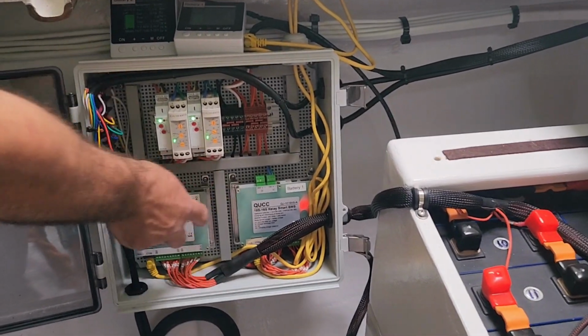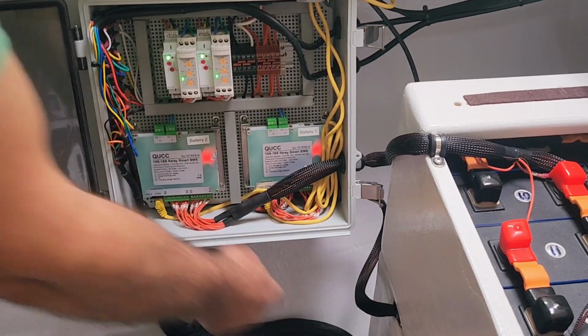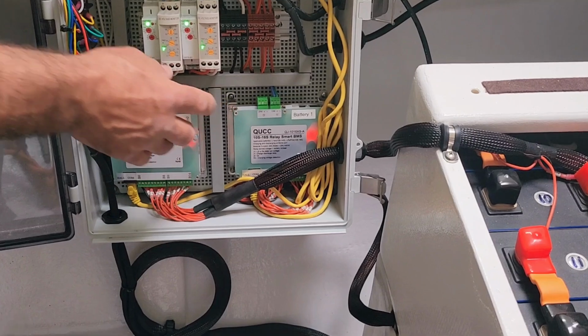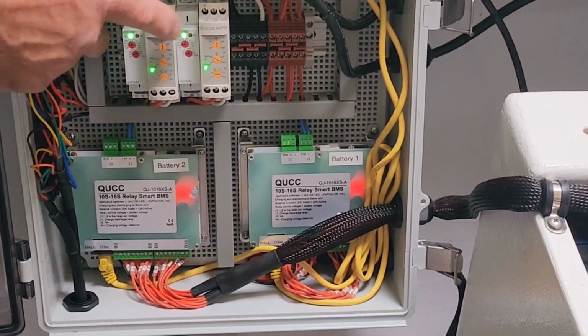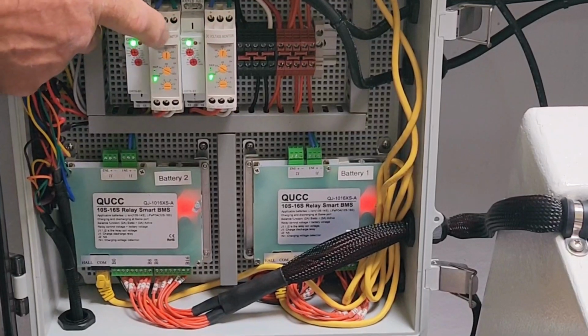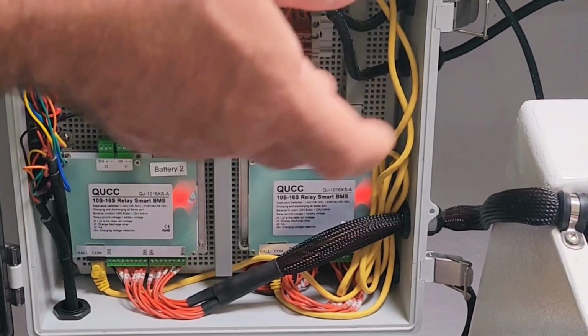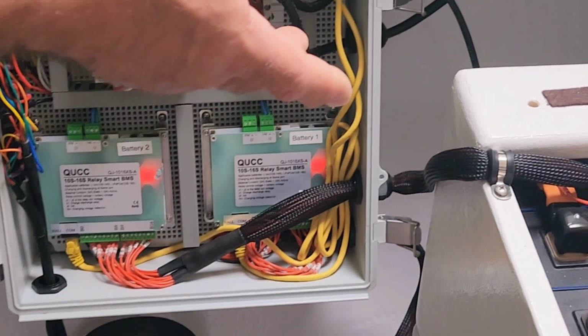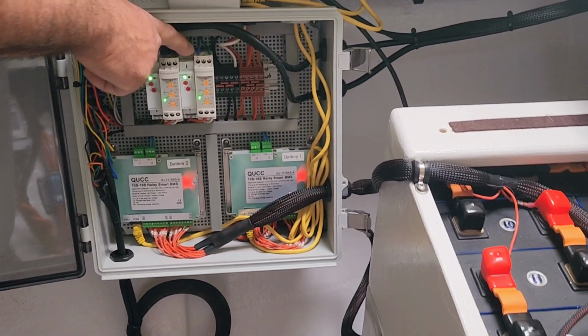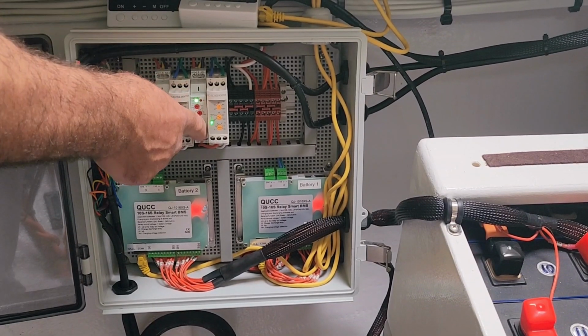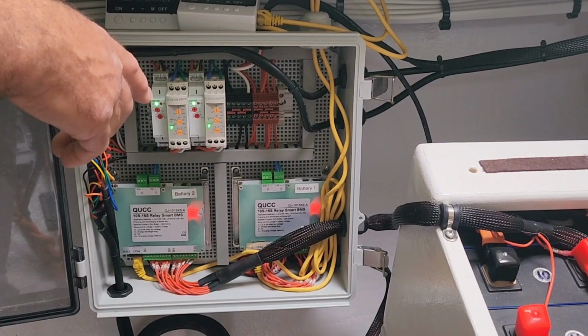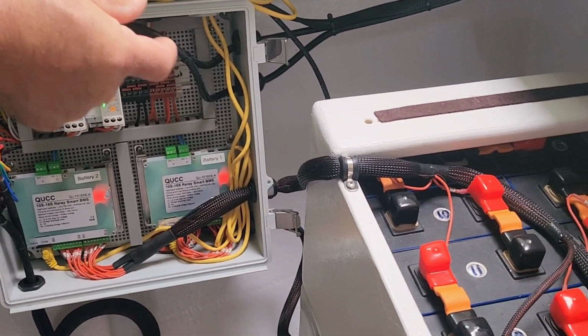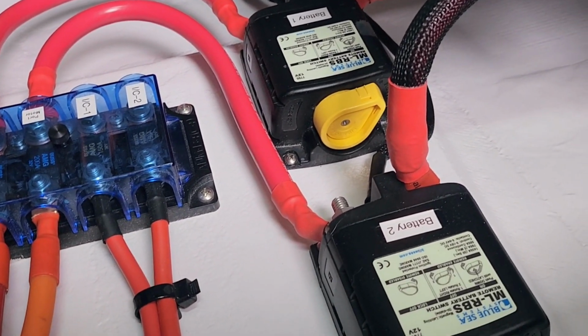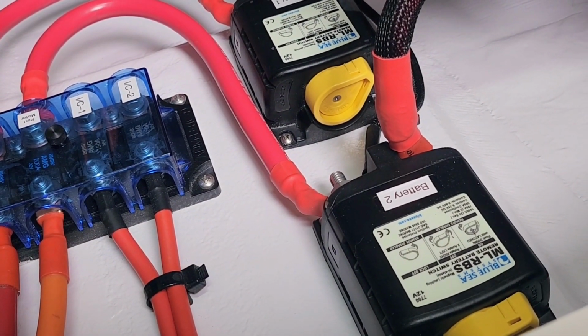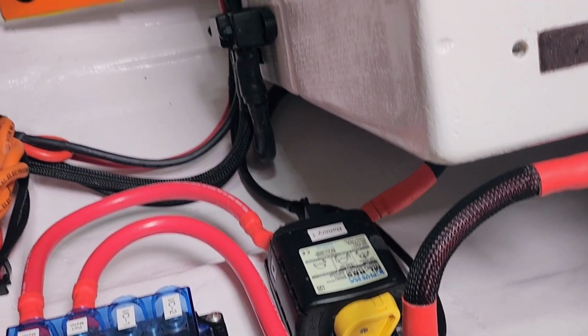What these battery management systems, and there's one for each battery, do is send a 48 volt signal to these relay clusters. If either of these relays for battery 1, battery 2 notice an anomaly, whether the battery voltage is too high or too low, they're going to send a signal to this time delay relay. The job of this time delay relay is to send a pulsed signal, a momentary on signal, to these battery disconnect relays. So instead of having a MOSFET that opens the circuit, we now have a relay.